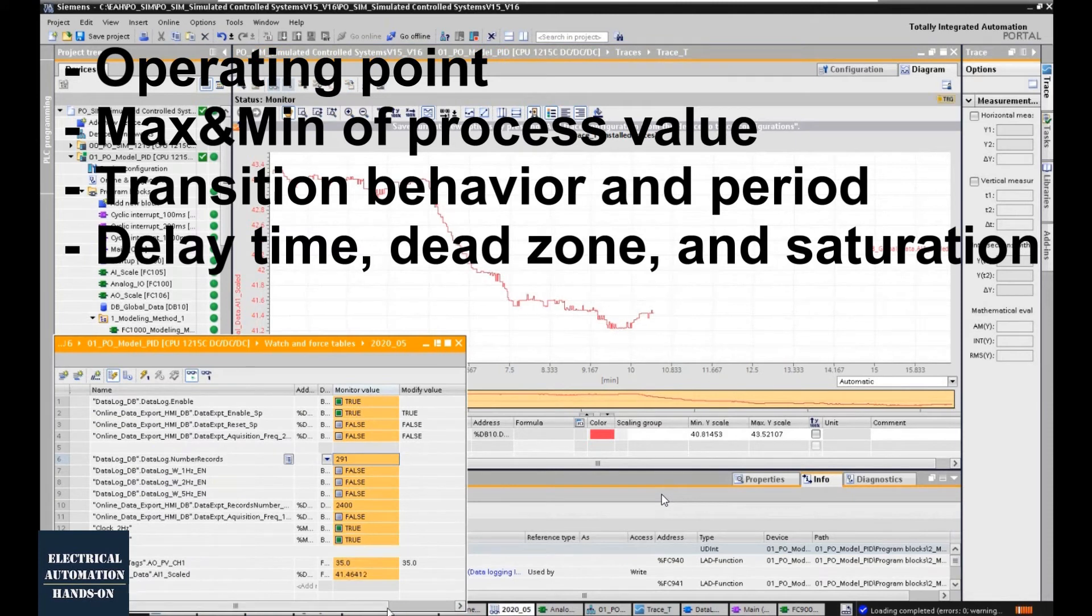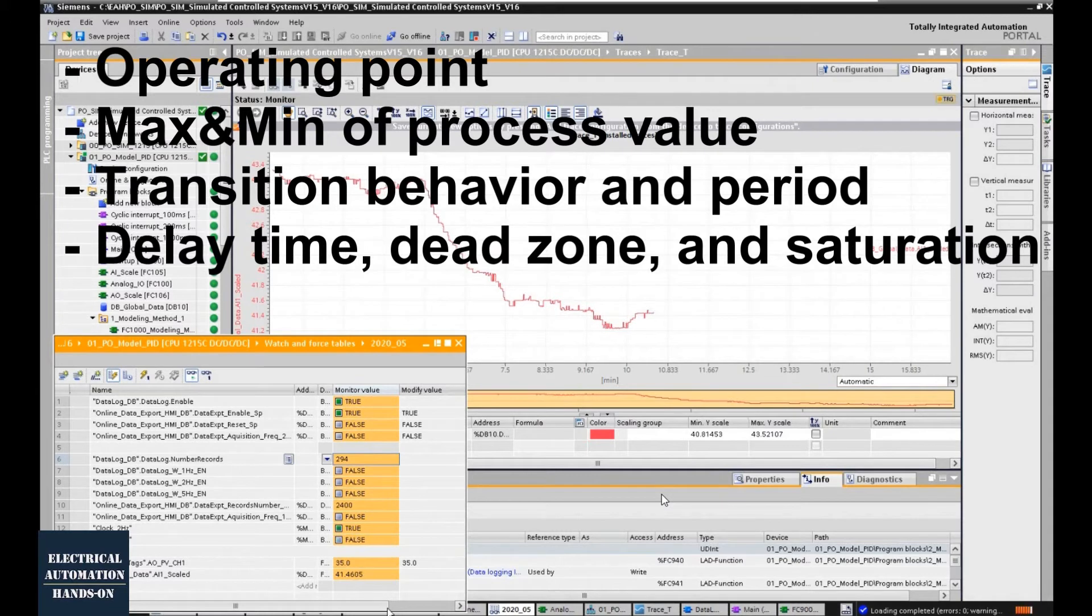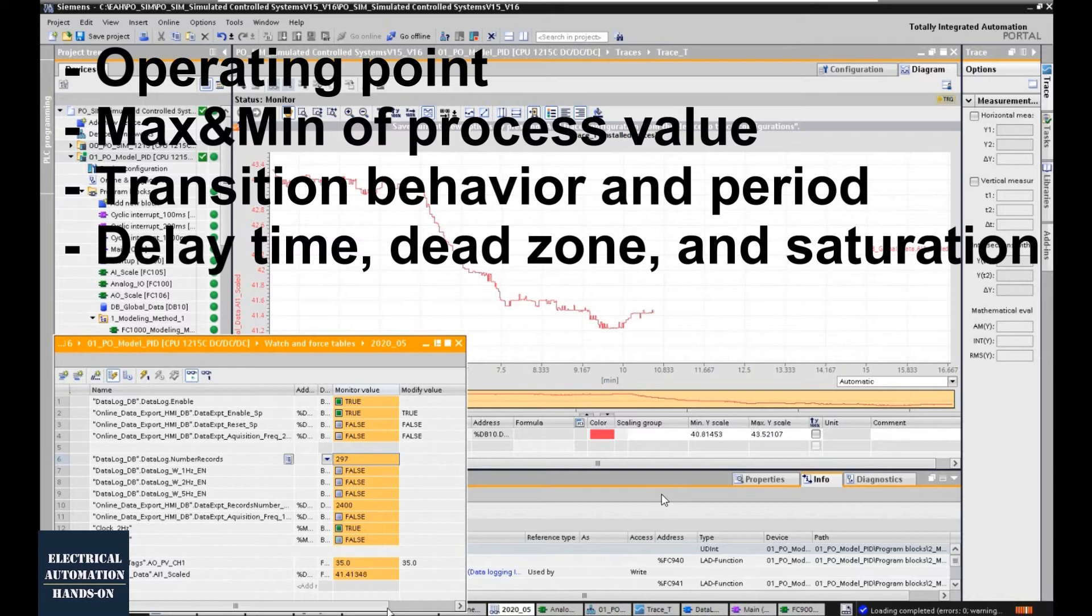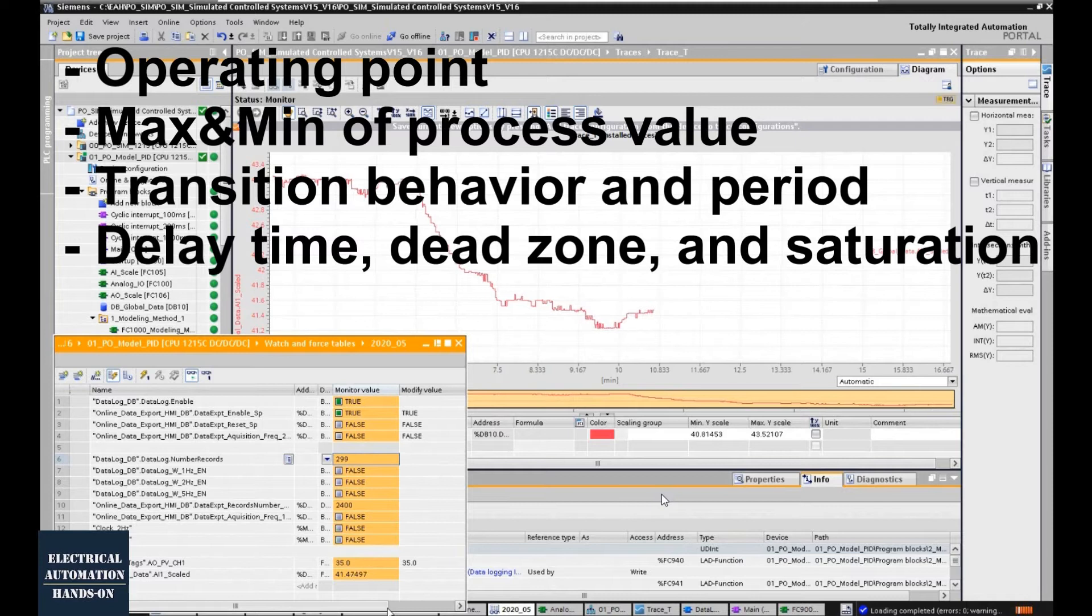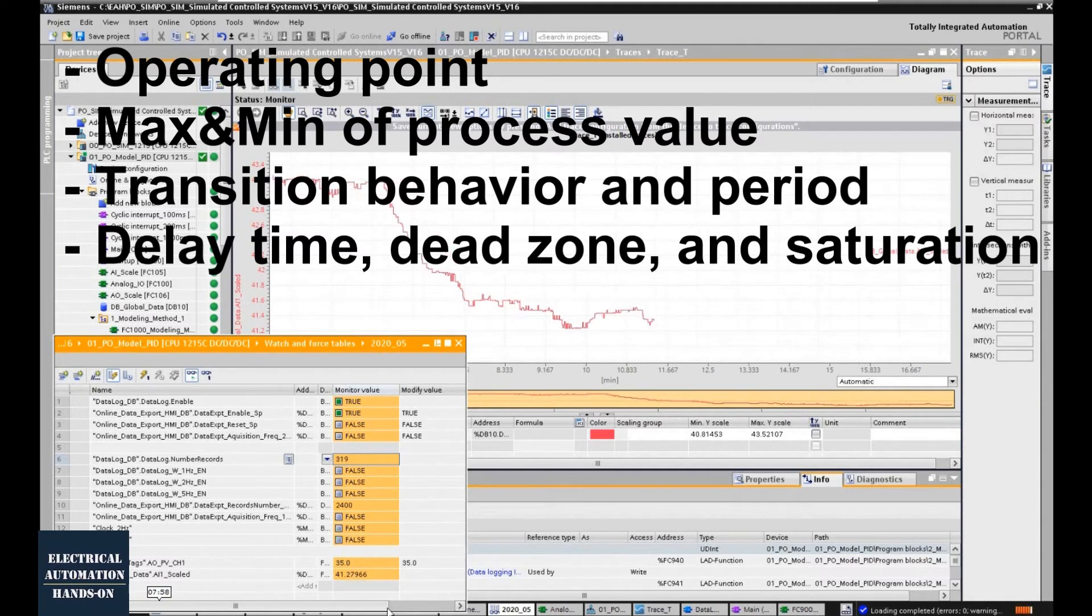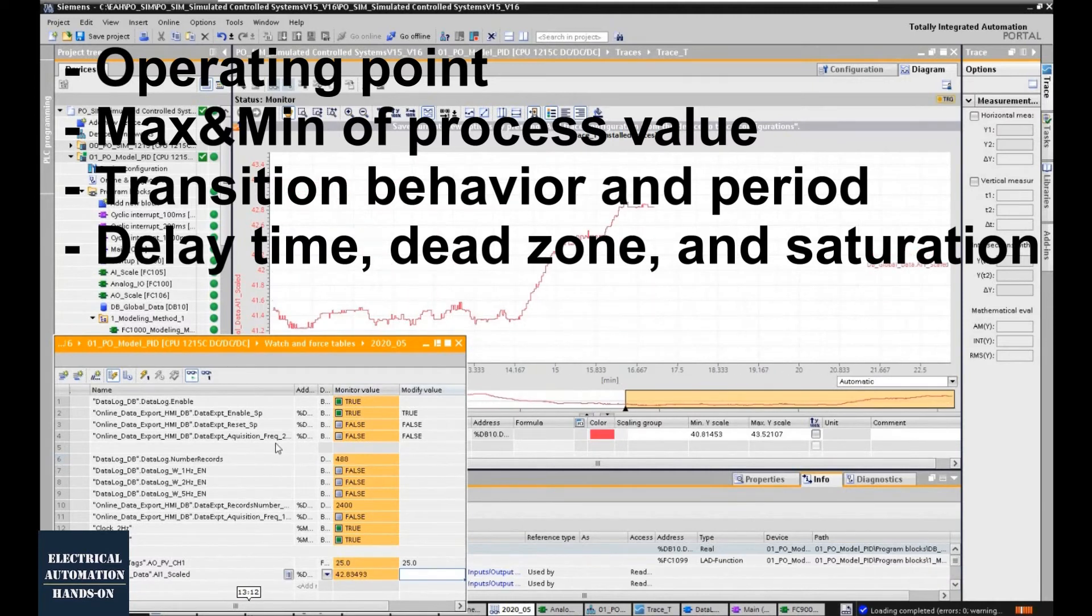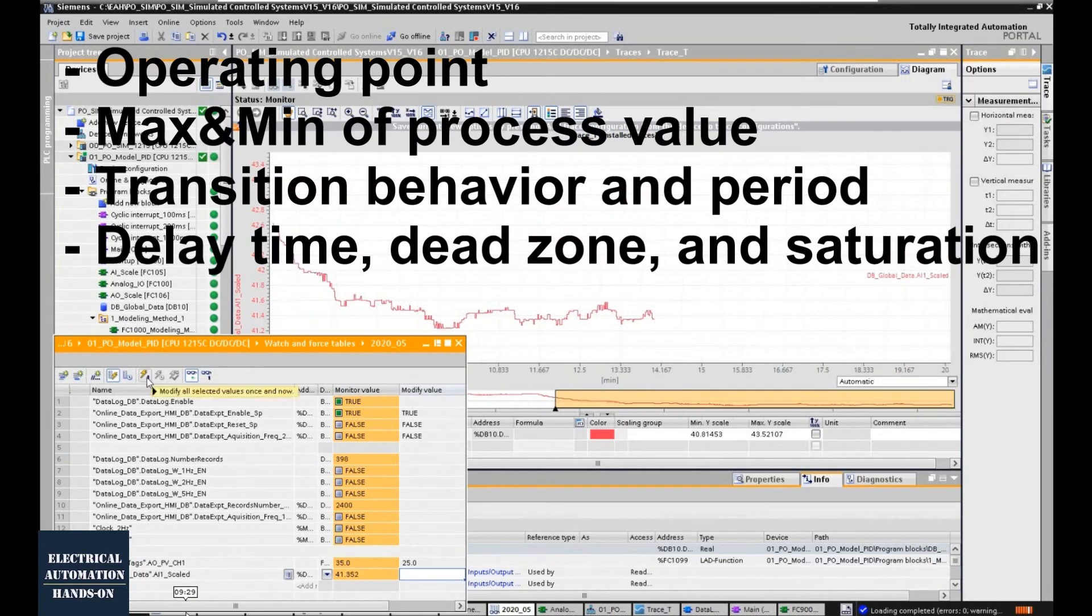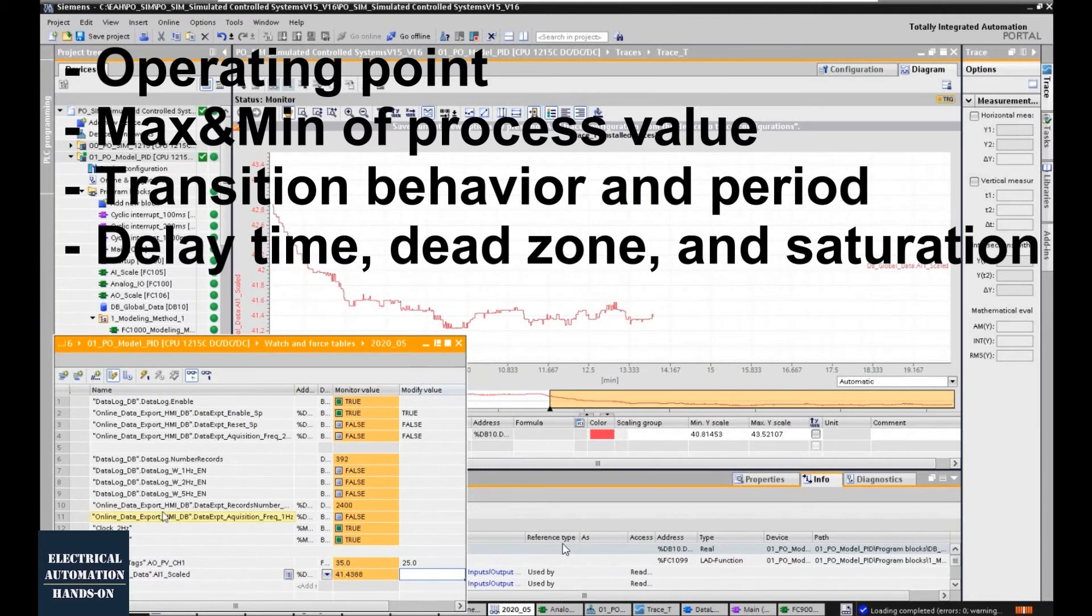And the fourth item is the delay time. That means every time you change the actuator, how long you would wait and see the behavior got a change from your system. Usually, this delay time maybe has a couple minutes, or maybe a couple seconds. The system has a response according to your actuator changes. Other than the delay time, we also need to take care about the dead zone and the saturation of your process behavior.